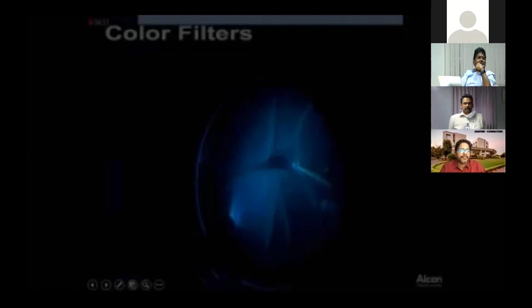The most important feature, which I personally feel, is the illumination which we are using for the surgical system. When you are operating, usually we sometimes go up to 100% of the illumination when we are visualizing through the microscope. Normally we use 30%, but in this, you can have a wonderful view of the fundus with just 10%. So the advantage is you can operate for a longer time in a complicated case.